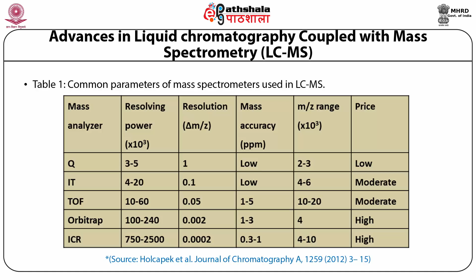Similarly, you can have different mass analyzers giving different resolution, and their mass accuracy is also given in ppm. You can see that Orbitrap is giving 1 to 3 ppm mass accuracy, and their price also ranges from low-priced mass analyzers available, and if you look at Orbitrap and ICR, they are priced highly and their resolution and even mass accuracy is better. Resolving power, which is commonly abbreviated as RP, is the basic parameter of quality of a mass spectrometer that characterizes the ability of the mass analyzer to resolve mass spectra peaks.